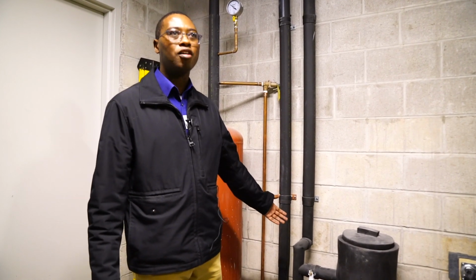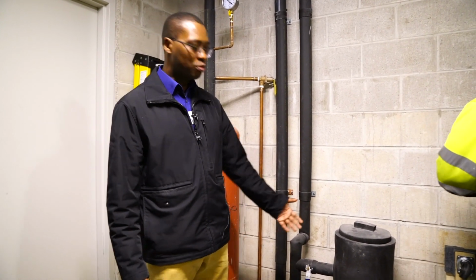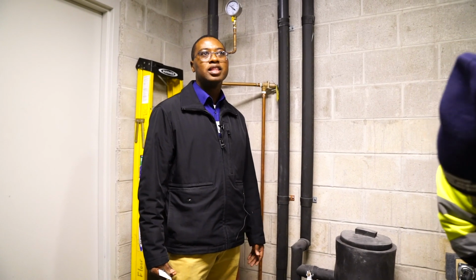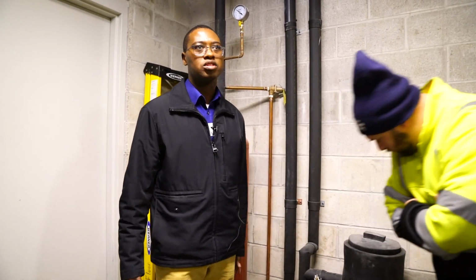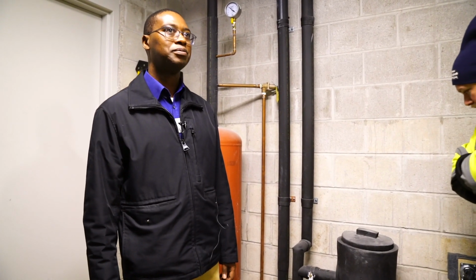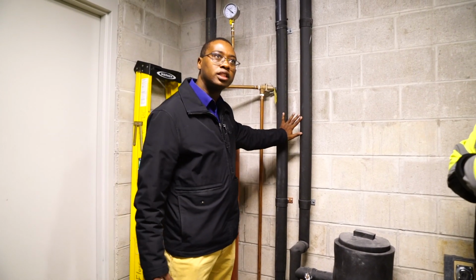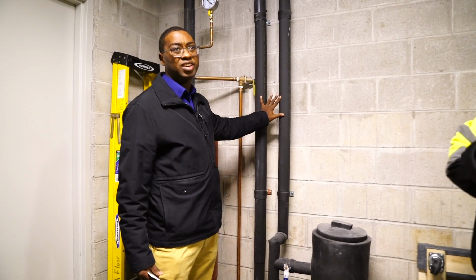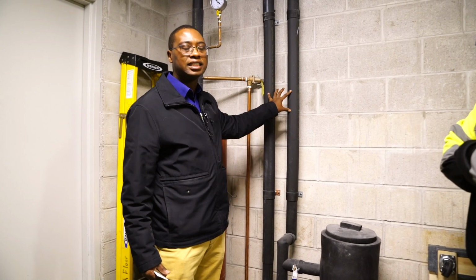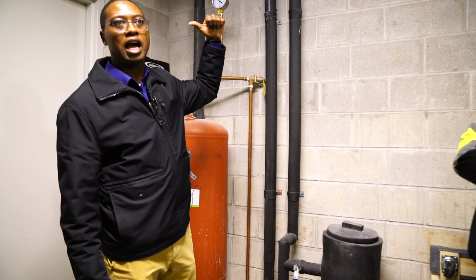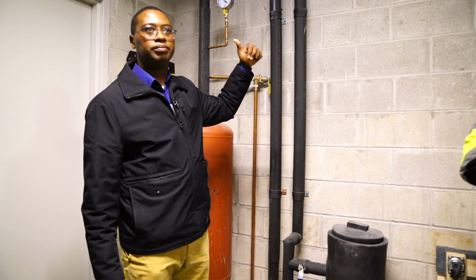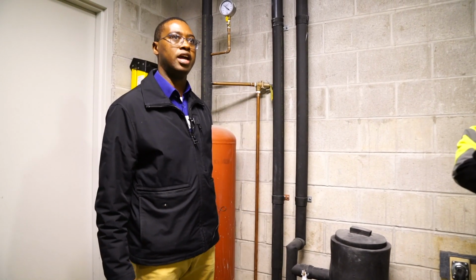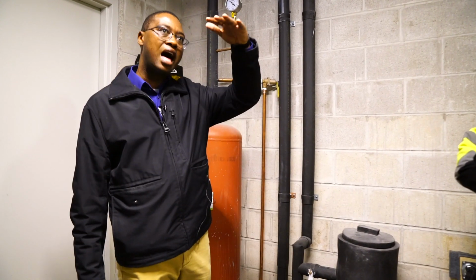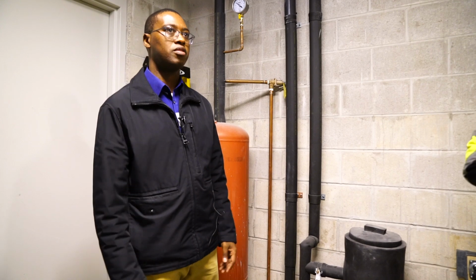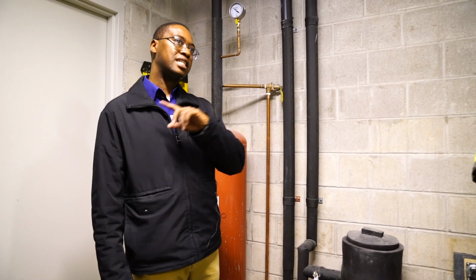But if I leave it off and use it when I need it, I prolong the life of it a little bit more than just having water running constantly. Make sense? All right. So this is for your chilled water system. It's also an F600 chemical. That is exactly the same chemical as the one that is in the hot water system. It's a nitrite-based chemical, and we maintain 500 to 1,000 ppm on those chemical ranges. So that's system number 2.